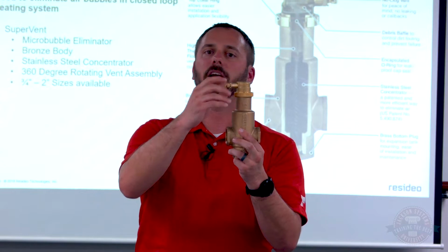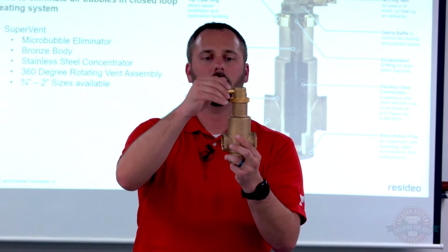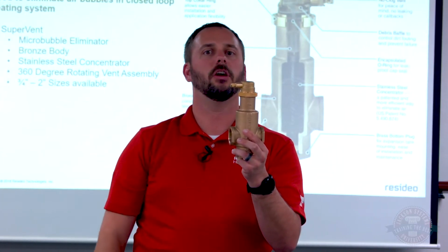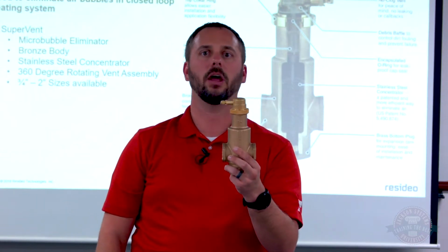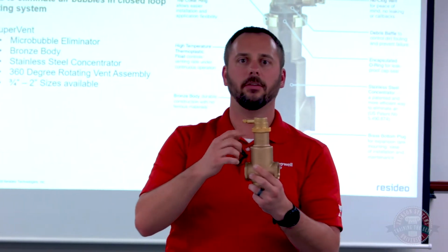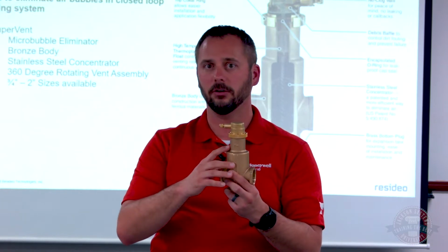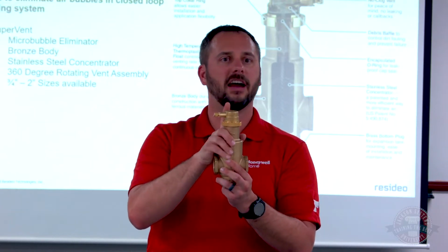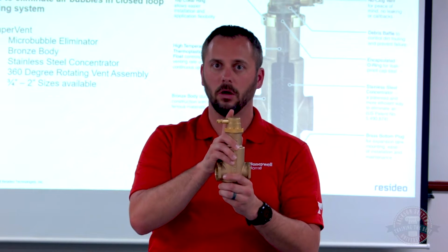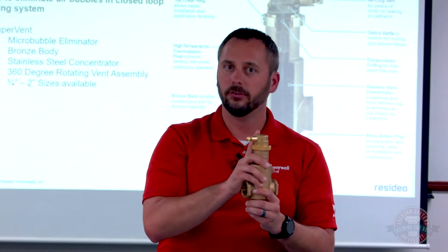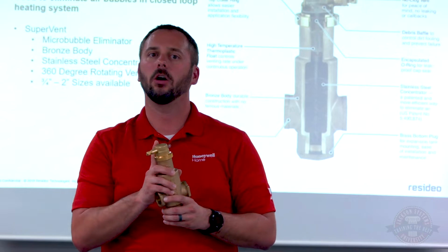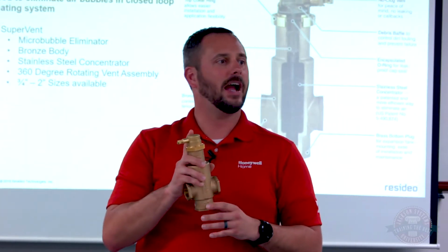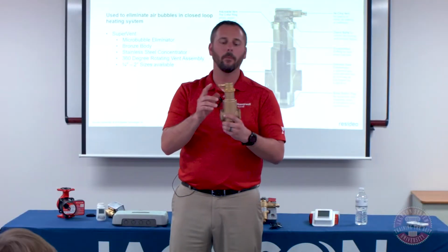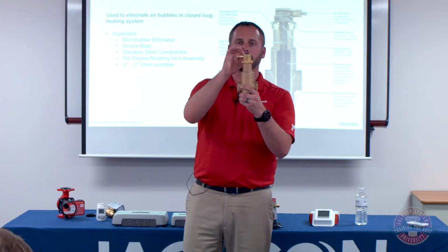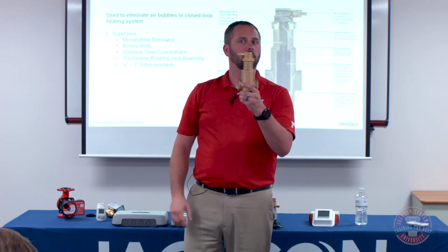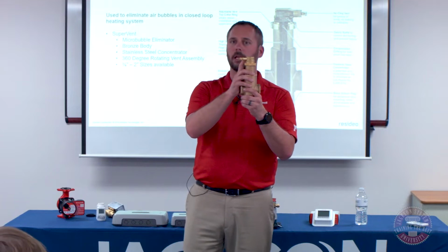The other thing you can do is, after you've gone through and done all your purging, you can shut this cap off just in case it may leak. But these are incredibly reliable. We redesigned the tip of this roughly 10, 15 years ago. It used to vent vertical. We did have problems with those leaking years ago, especially on glycol systems. For those of you that use glycol, you know it has a way of finding leak paths that water doesn't. So when we redesigned this head and the guts inside of here, it doesn't matter if you're using glycol or water. We don't have issues with these leaking anymore.